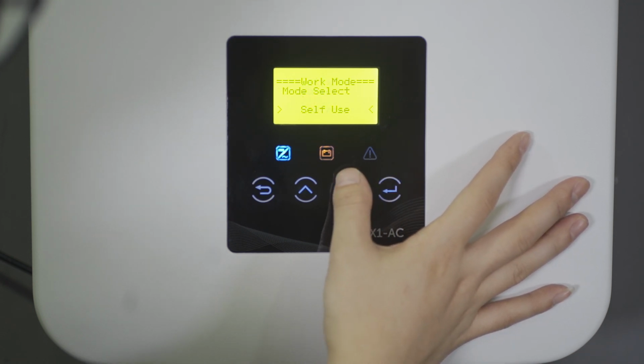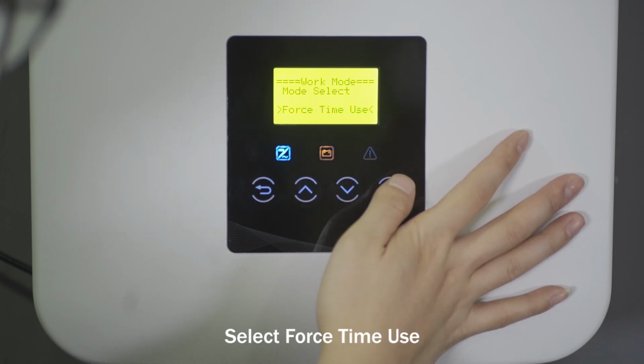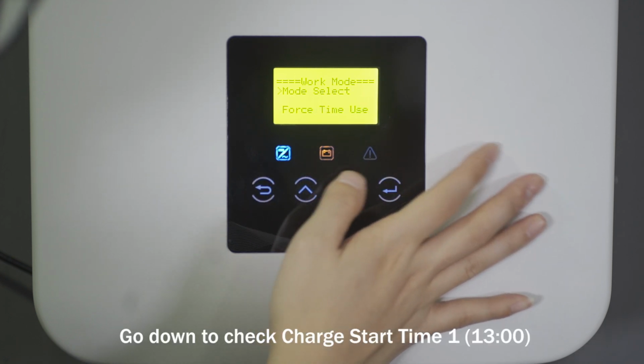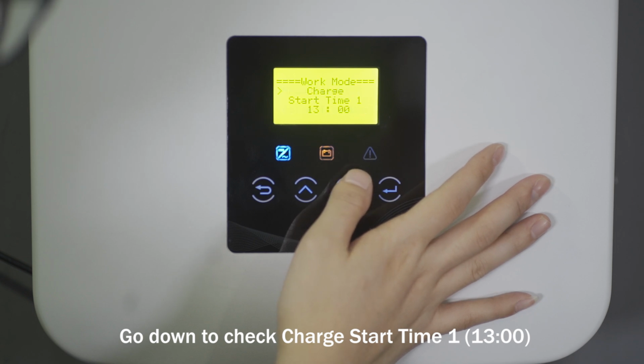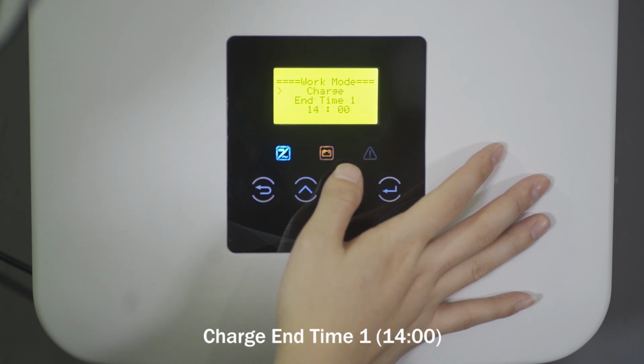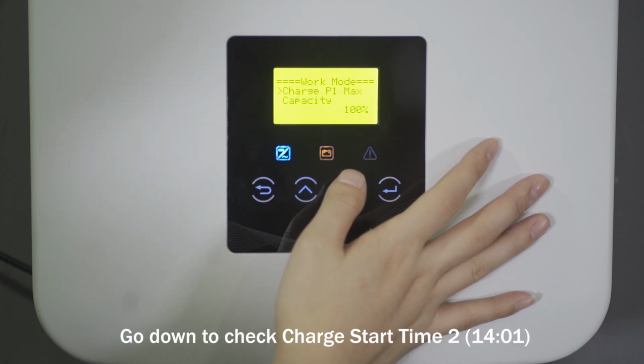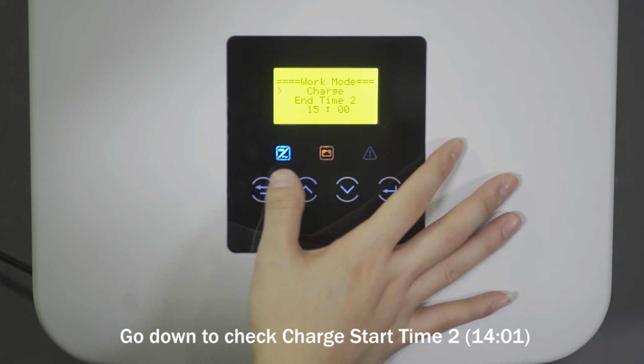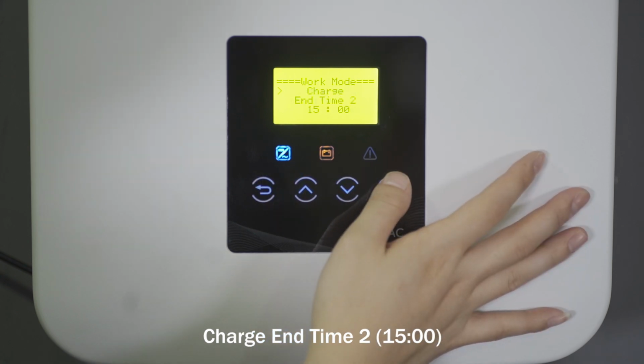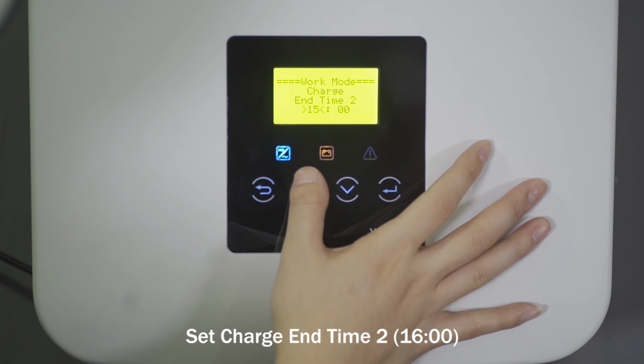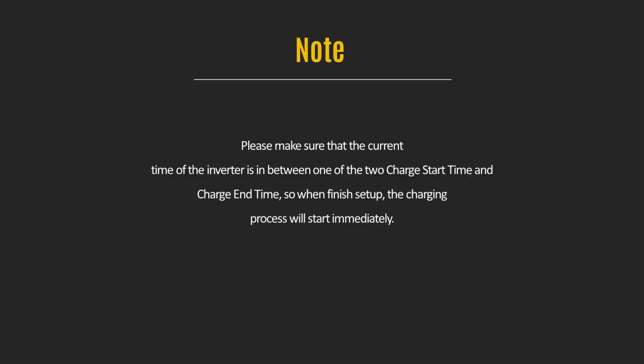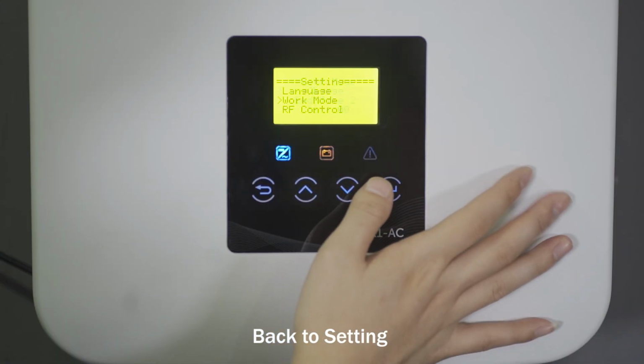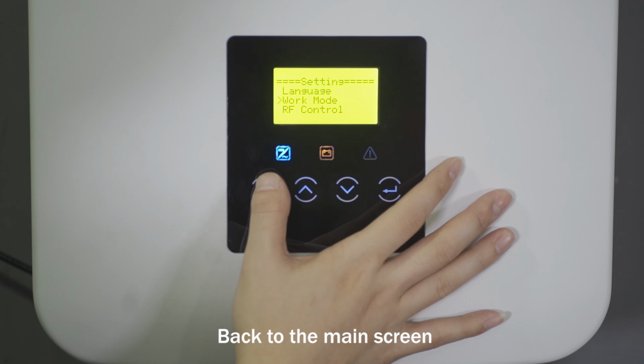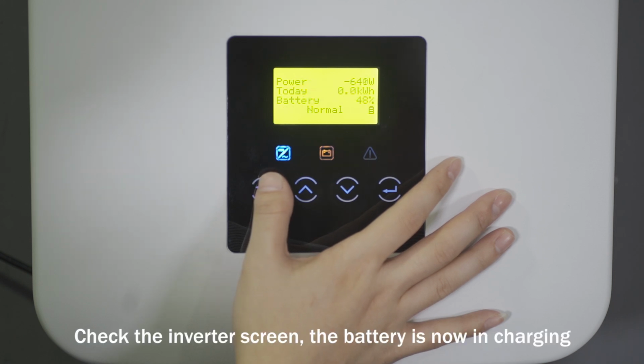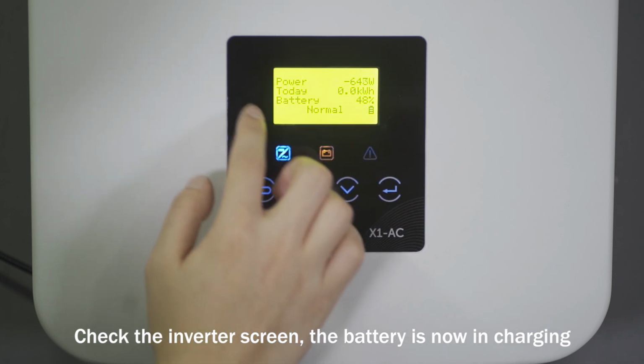Enter work mode. Select force time use. Go down to check charge start time 1. 1300. Charge end time 1. 1400. Go down to check charge start time 2. 1401. Charge end time 2. 1500. Set charge end time to 1600. Back to setting. Back to the main screen. Check the inverter screen. The battery is now in charging.